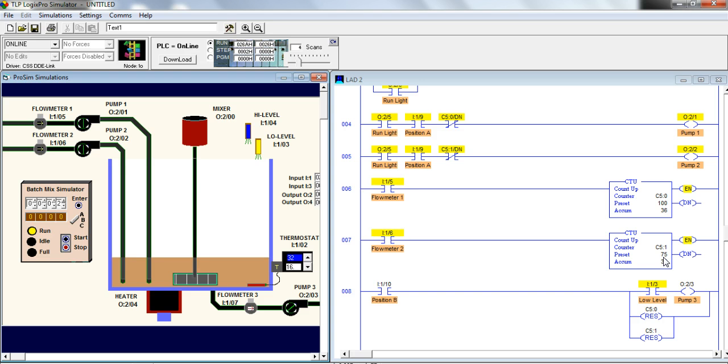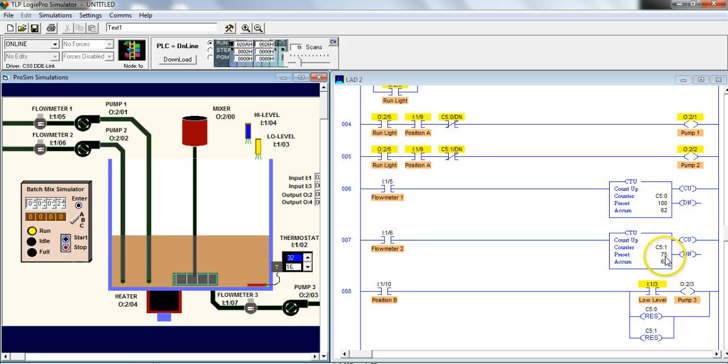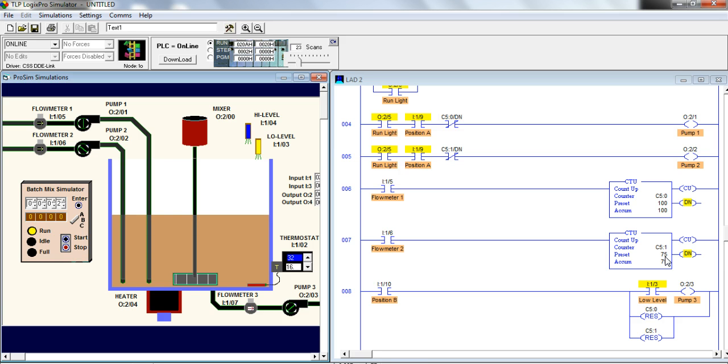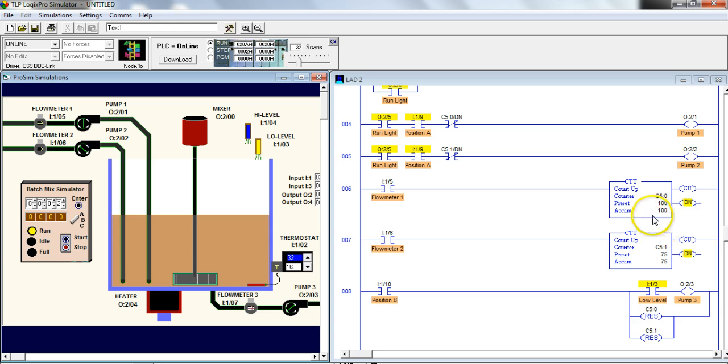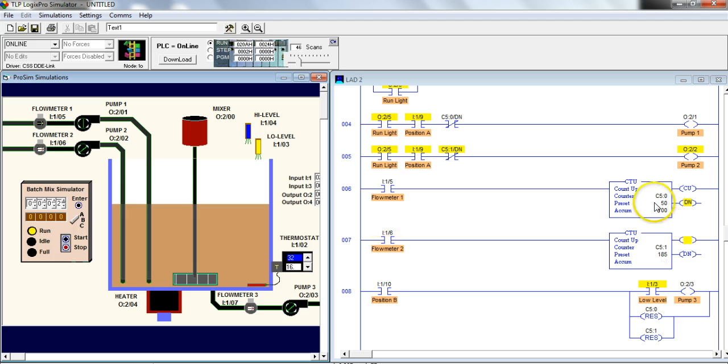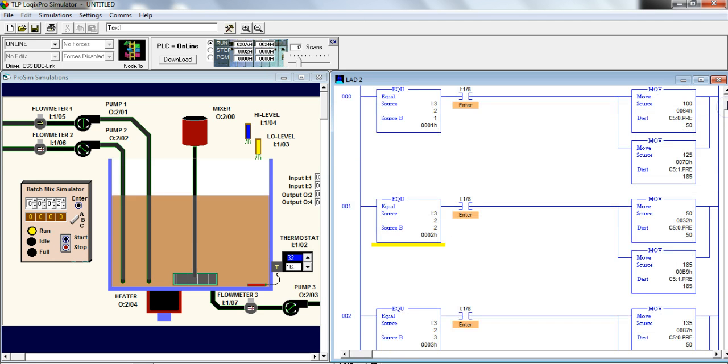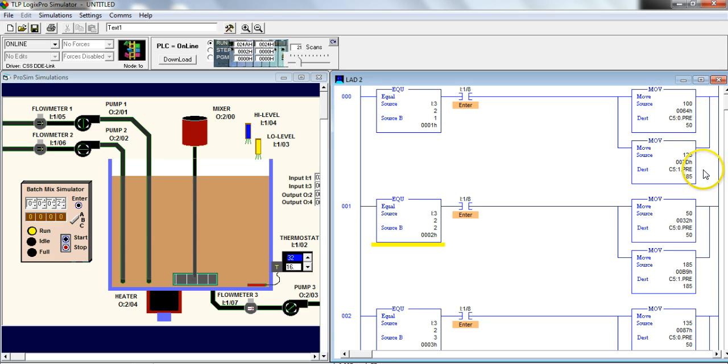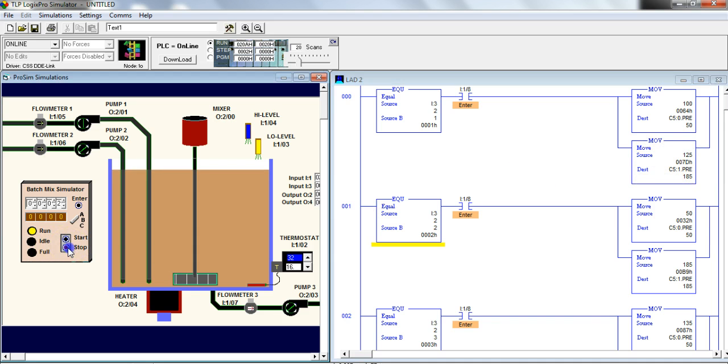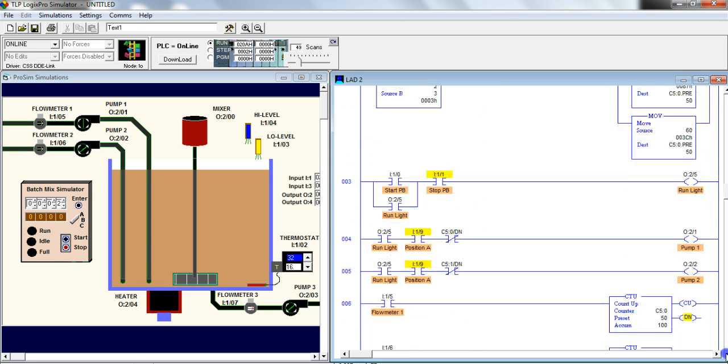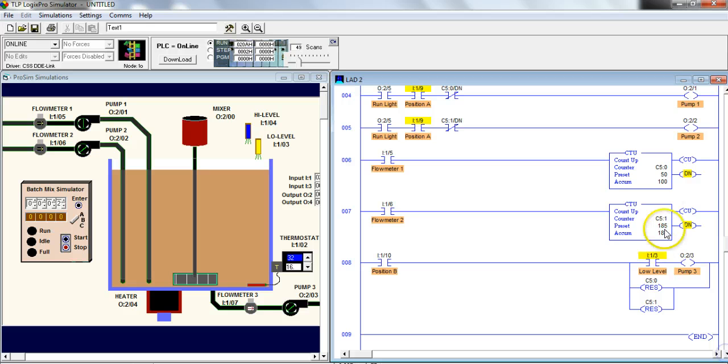But what you need to do is you need to find out where these actually are coming from. So anytime you're thinking about changing any kind of data within the PLC, whether it's a counter or whatever it is, cross-reference this back and find out where this data is coming from. Because what you're going to see is as soon as I push enter right now, these changed and went back to the move source data. So, you know, this is a great example of a move instruction. And one other important thing to remember about move instructions is a lot of times that's where data is coming from. So you can't just go and change data here if it's coming from a move instruction.